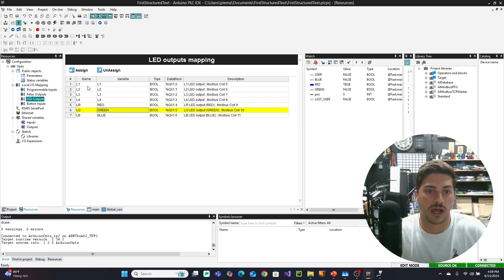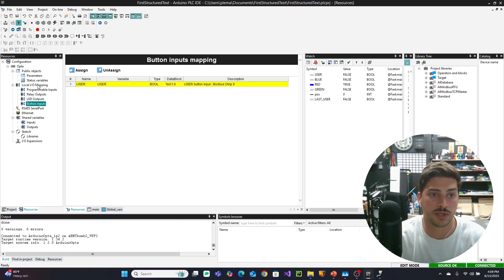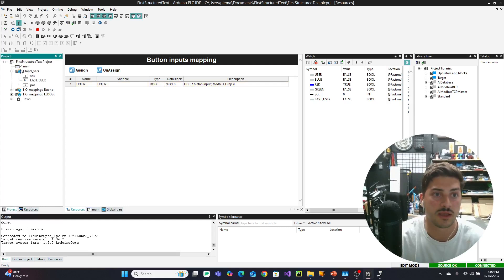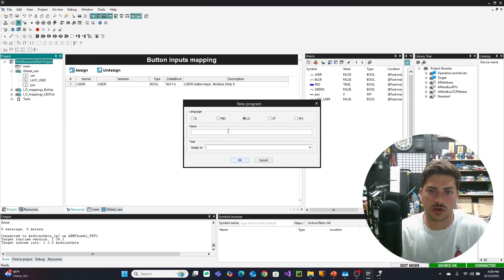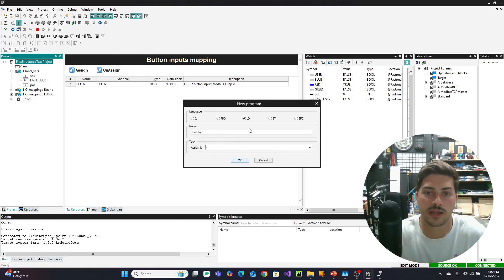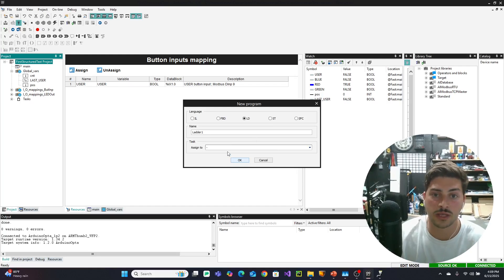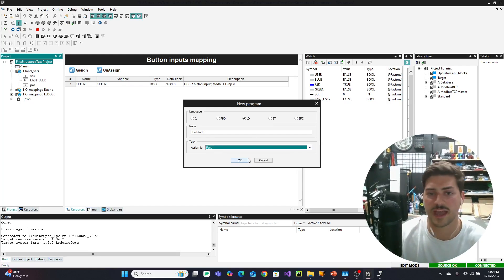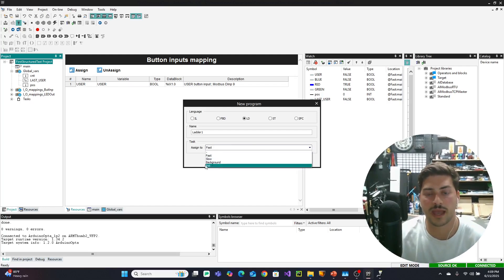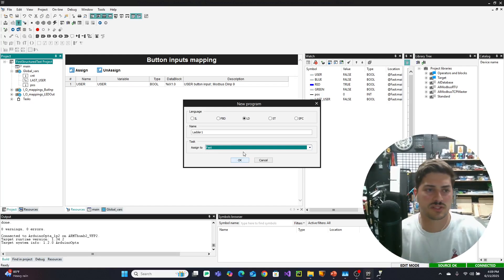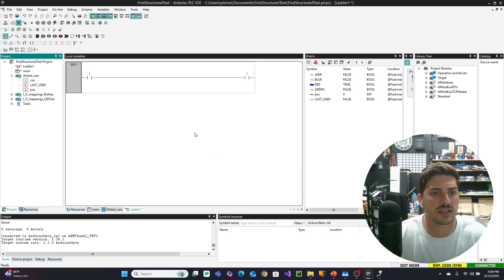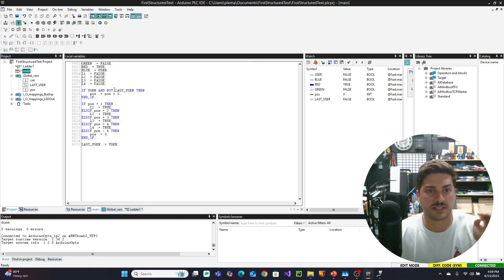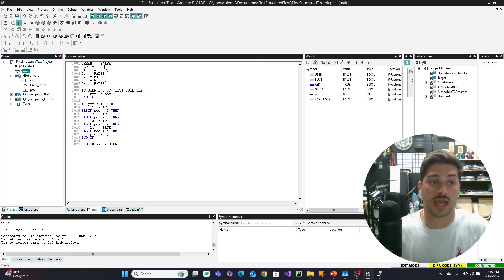So with that basic setup, with these variable names, with these button inputs, let's go ahead and go to project, and let's go to add new program, and we'll call this ladder 1, because I might do more ladder. And make sure you have LD, ladder diagram selected. Structured text was what we did in the last video, and we're going to assign it to fast. So these are different scan rates, fast, slow, background, and init. We're going to assign it to fast, no reason not to go fast.